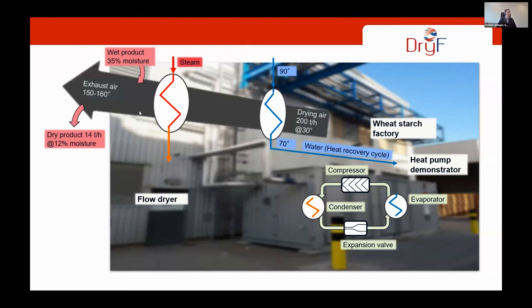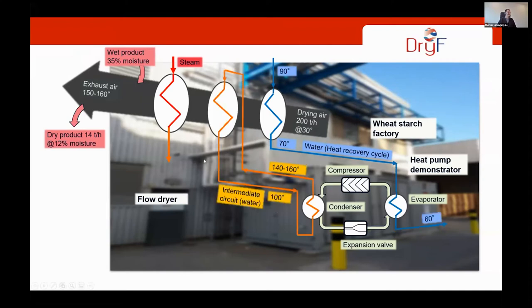And the overall capacity is something around 14 tons per hour of the dryer. So the integration was done like this. You can see now we have filled the gap here between these two existing heat exchangers by a third one, where the intermediate circuit, a water cycle coming from the condenser side, goes up to 140-160 degrees Celsius, which gives us a little bit lower steam demand on the dryer itself.